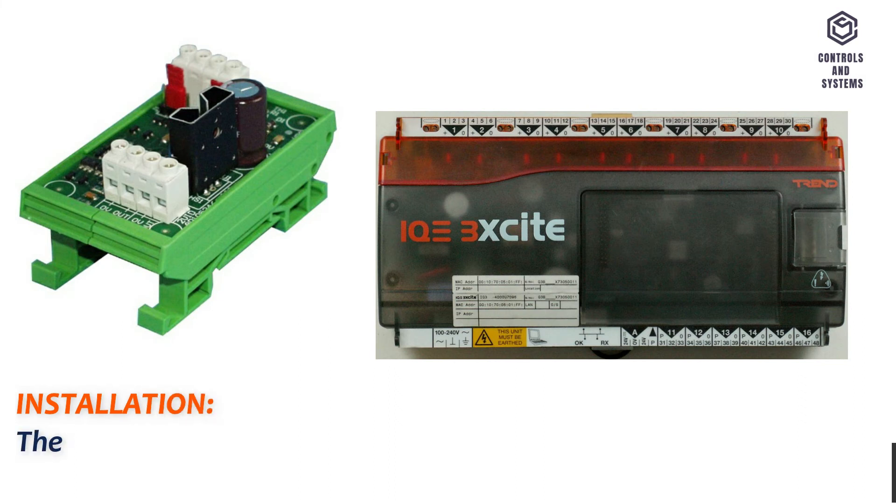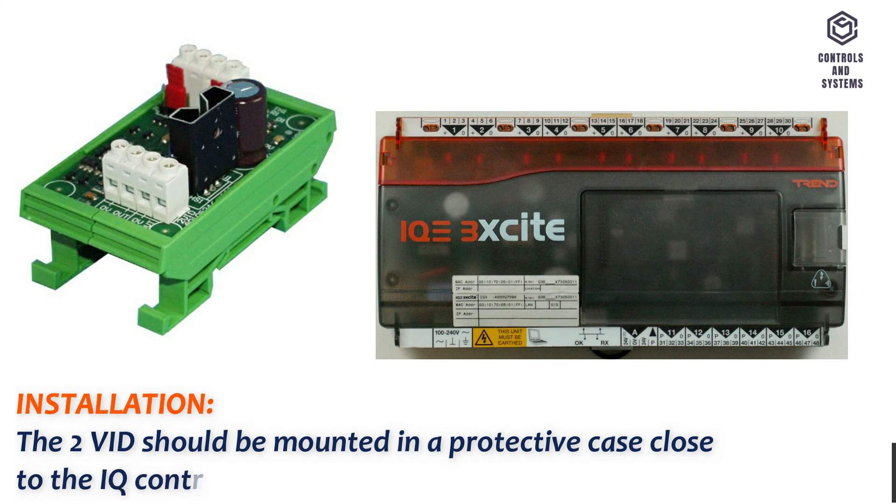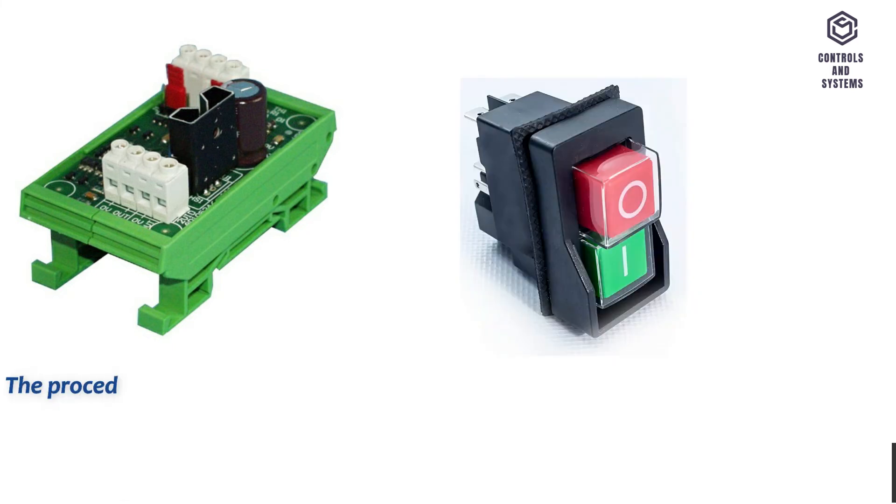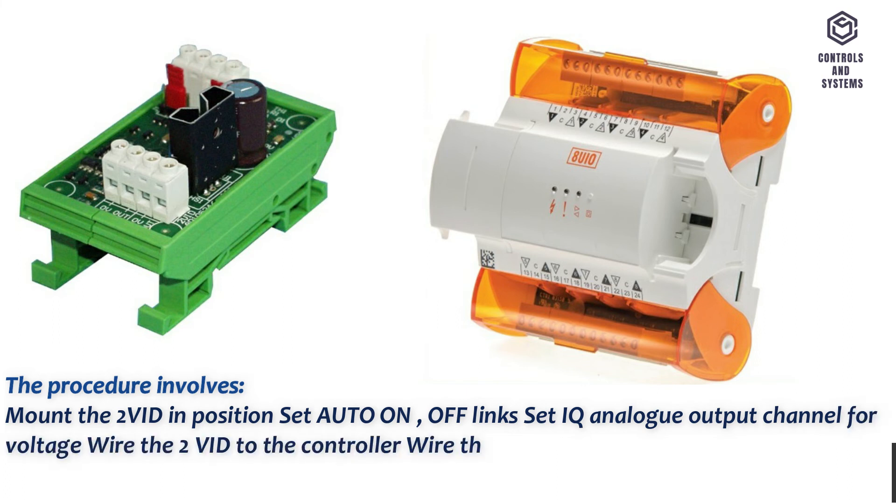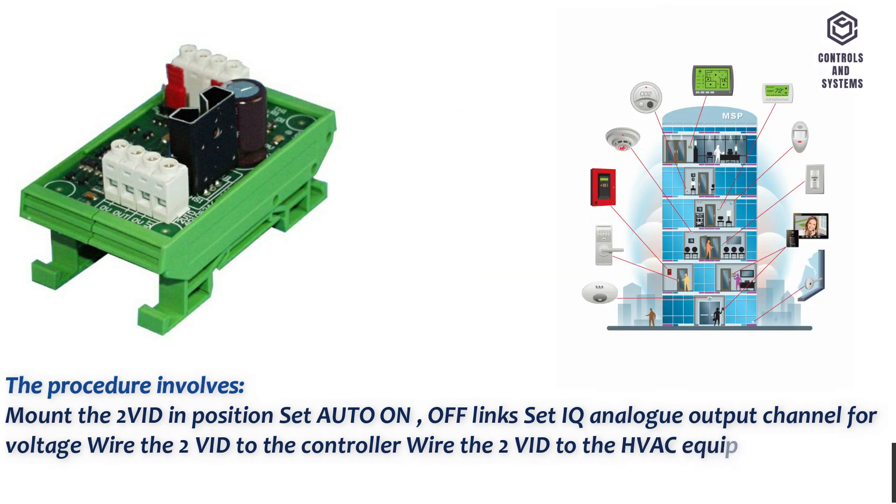Installation: The 2VID should be mounted in a protective case close to the IQ controller. The procedure involves: Mount the 2VID in position, set auto on/off link, set IQ analog output channel for voltage, wire the 2VID to the controller, wire the 2VID to the HVAC equipment, connect the 24V supply, check interface operation.